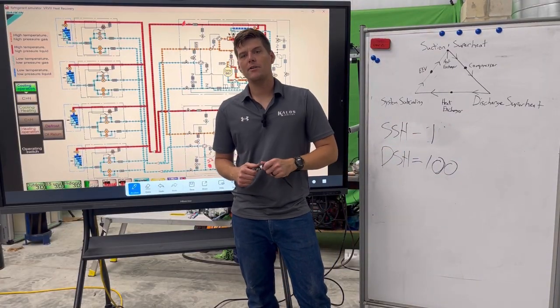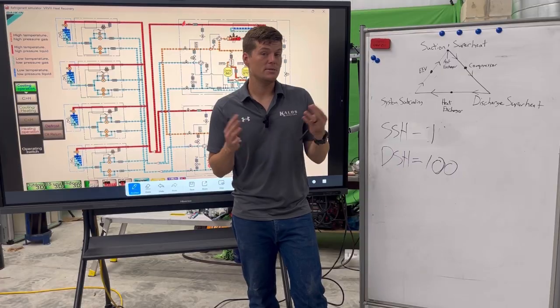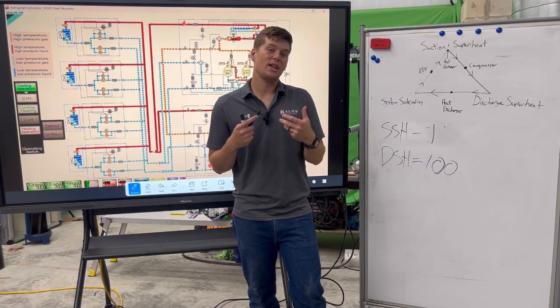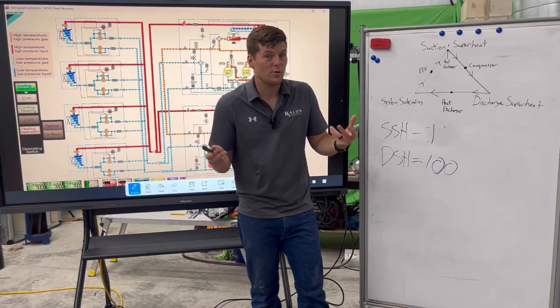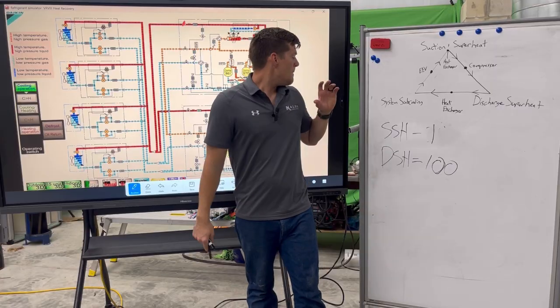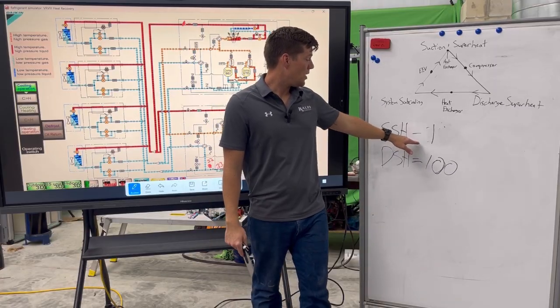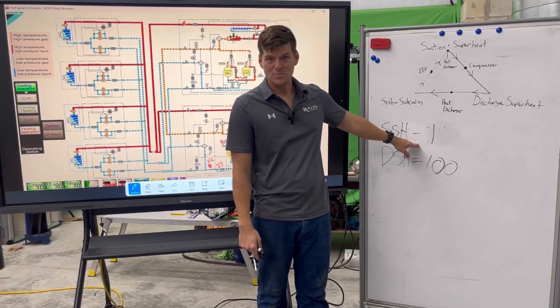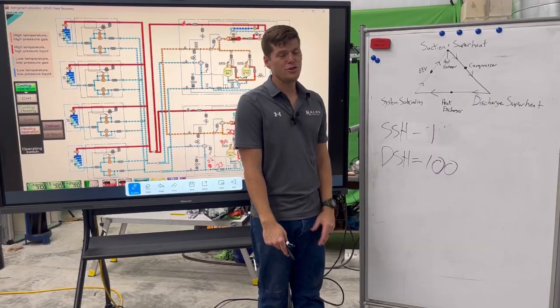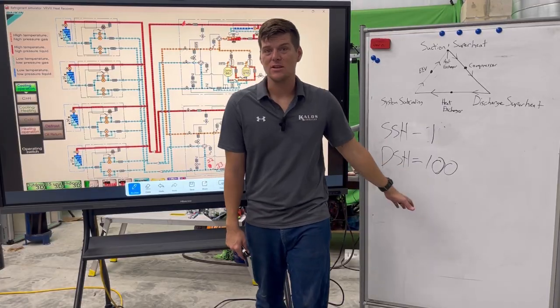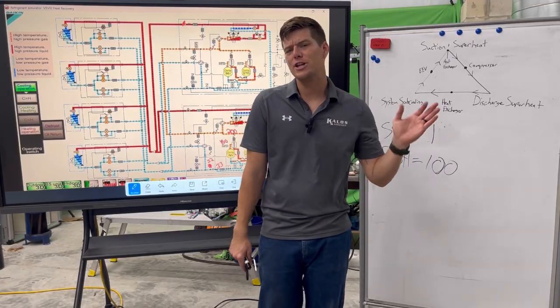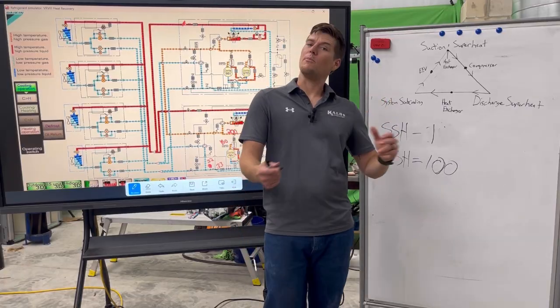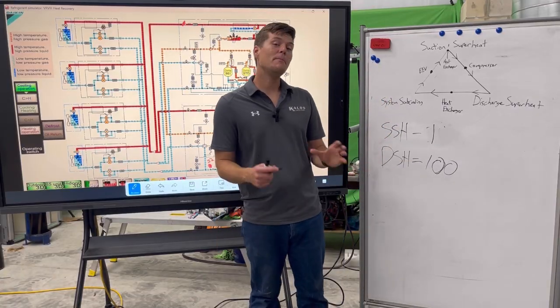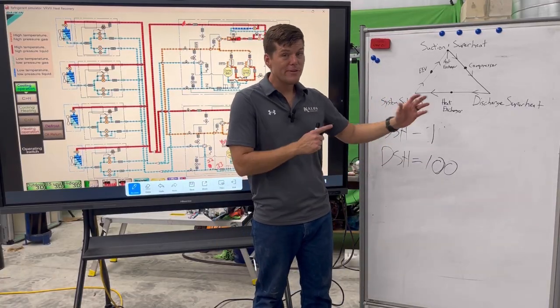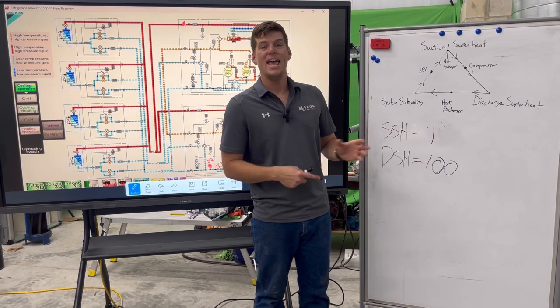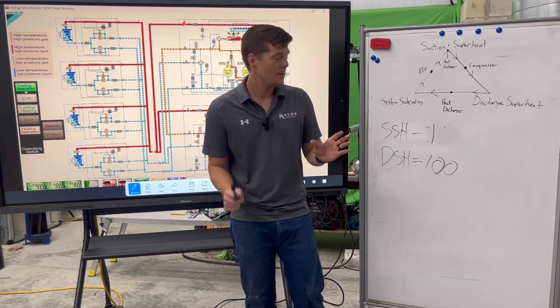Well, so here's the thing about vapor pumps. When they get liquid in them, one, it's bad. The scroll plates will actually disintegrate if they get a large enough liquid in them, or if they have a flooded start. But with this, we know we're getting way too much refrigerant back to my compressor. So my discharge superheat should be in the toilet. It should be 5 degrees. It should be 10 degrees. It should be anything below 32, right? Because again, we're compressing liquid. We're getting a mixture of liquid back to the compressor. And it's a vapor compressor. It's not designed to compress any mixture of liquid of any amount.